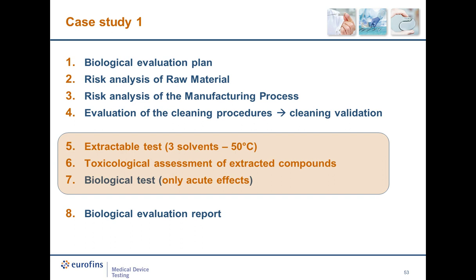Next is the risk analysis of the manufacturing process, investigating each manufacturing step. Then the evaluation of the cleaning procedure that leads to cleaning validation. The fifth step is the main extractable study using three solvents and 50 degrees as extraction temperature, as requested by FDA guideline. The extracted compounds are later on toxicologically assessed and in case of no relevant concern, only a few biological tests are performed, focusing only on acute effects.